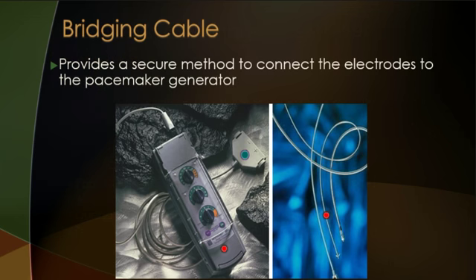So the parts of a pacemaker: the bridging cable is, if you look on this picture, you'll see a red dot. This is the device that we use to secure the electrodes to the pacemaker generator. You can also, if you didn't have a bridging cable, there's also holes on the top of the generator that will allow you to plug your electrodes directly into them.